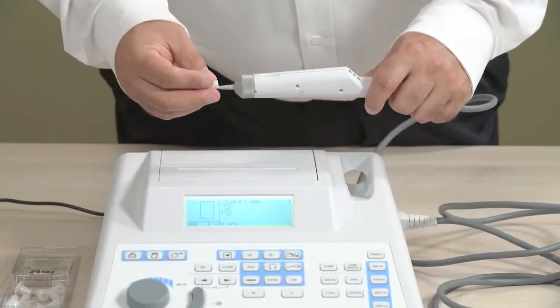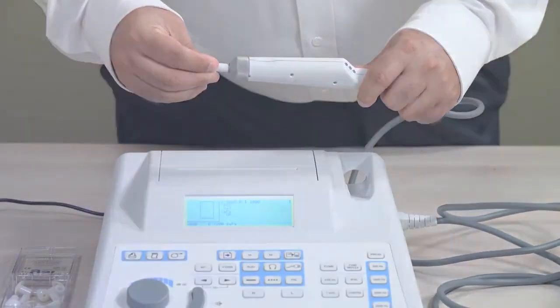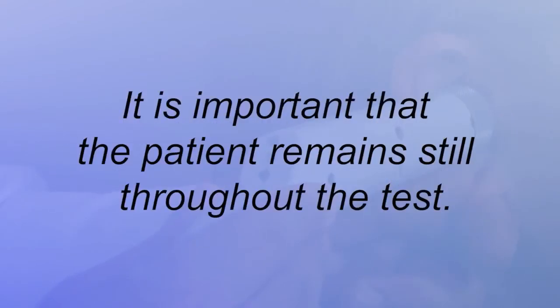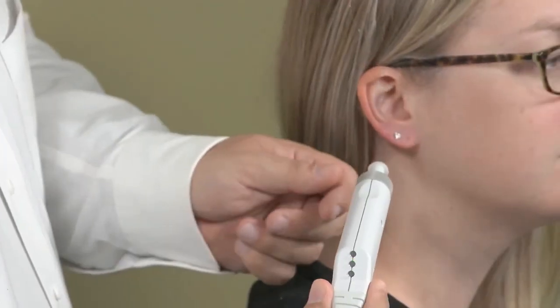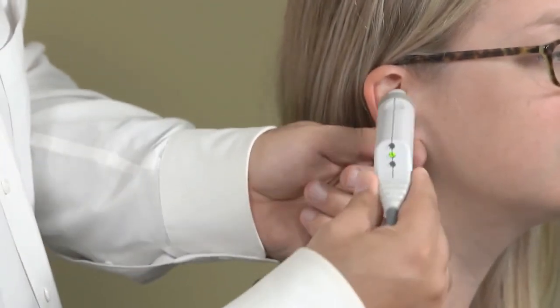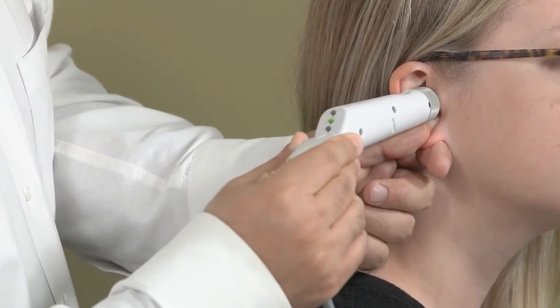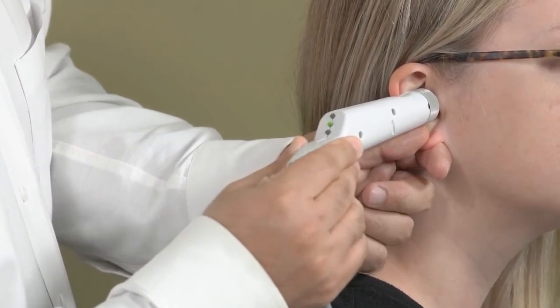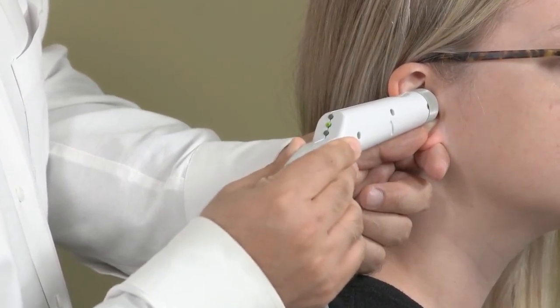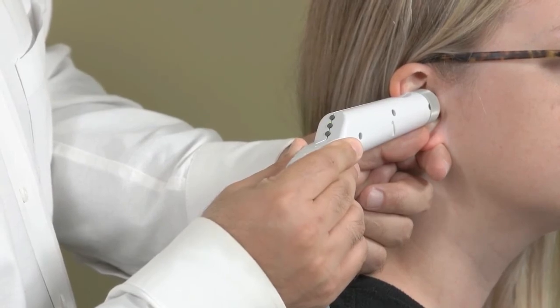Once the tip is attached, it is ready to begin testing. Tympanometry is designed to start testing automatically. It is important that the patient remains still throughout the test. When a good seal is obtained, the blinking green lamp will change to a steady glow and remain steady while the test is in progress. When the test sequence is over, all lights on the probe will turn off.